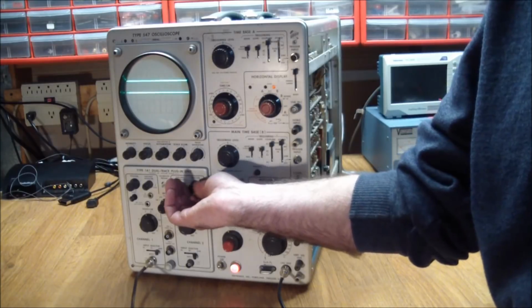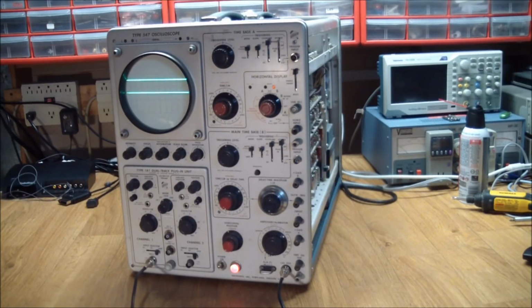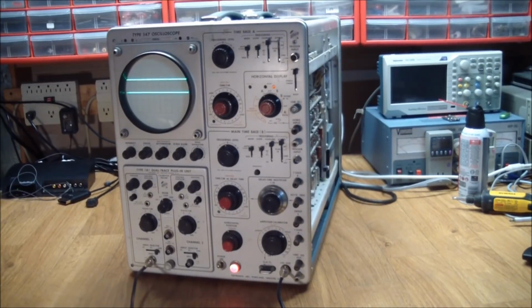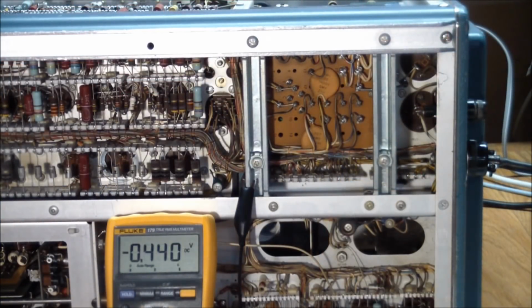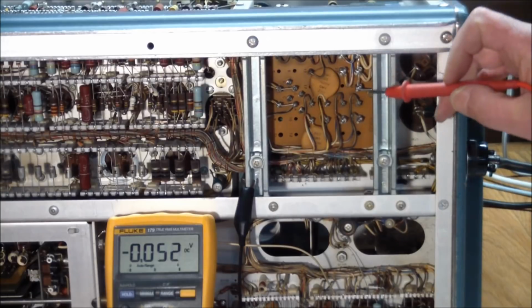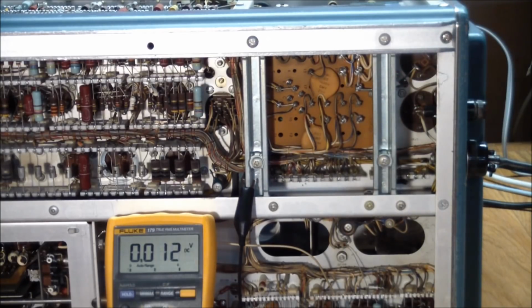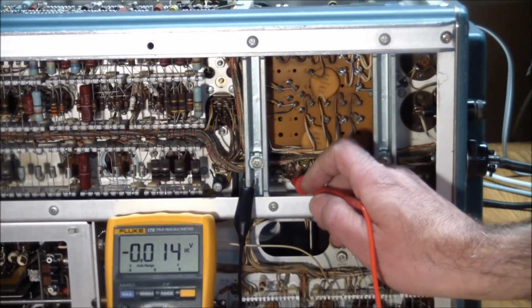So something here is out of kilter, and probably the first step would be to check the power supply voltages, and we probably need to clean some tube sockets too in here. Well, tube pins actually, but let's have a look at the power supply voltages first. Well, let's measure some voltages, starting with DC.